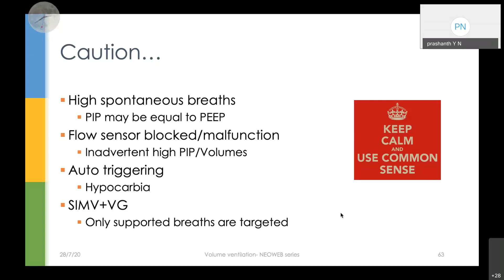In SIMV with VG, we need to understand that only the supported breaths are targeted. The ventilator lets the baby breathe in between, since those breaths are not in its purview. Those are the breaths which the baby has to work for. The ventilator is not giving a guarantee to the spontaneous breaths in this SIMV mode of ventilation, where they are not supported. Only the supported breaths are volume guaranteed.